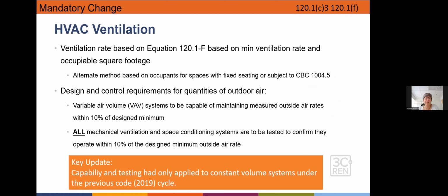For HVAC ventilation, under the previous code cycle, most of the ventilation controls really had applied to constant volume systems, but now they're being applied to variable air volume systems, and they're being applied to the dedicated outdoor air systems. The ventilation rate itself is still based on ASHRAE 62.1 and based on the equations that can be found in section 120.1 for minimum ventilation rate.